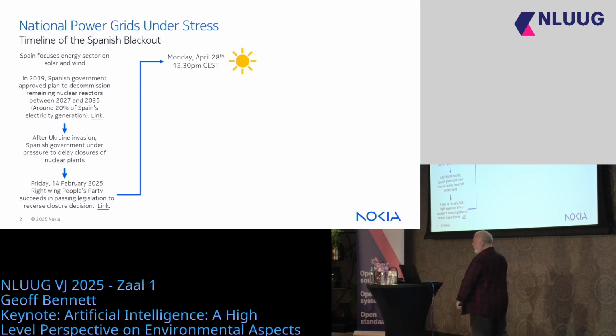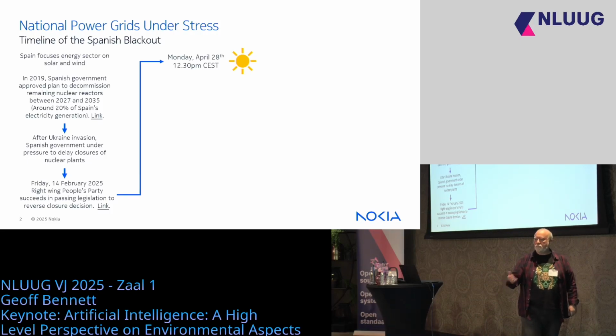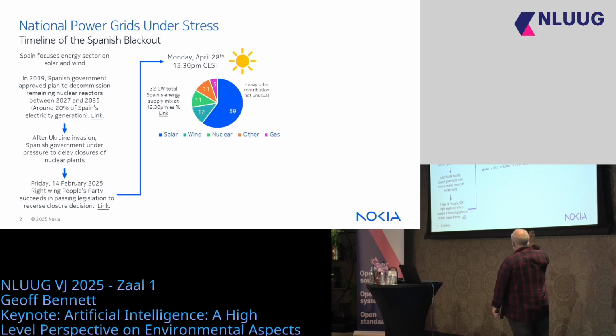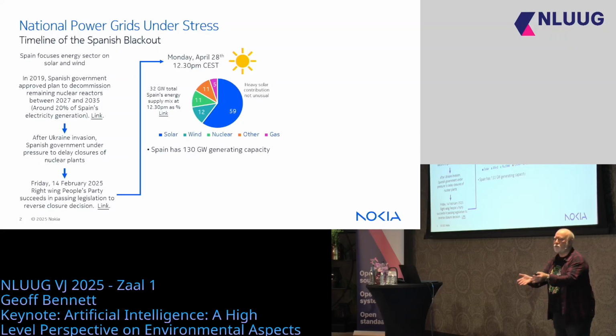So let's fast forward to April the 28th at 12:30 Central European Summer Time. What's happening in Spain? It's a beautiful sunny day. The energy mix in Spain is about 71% solar and wind. The rest of it comes from a little bit of natural gas, a little bit of nuclear. And if we look at Spain, they don't have a problem with the amount of power they can generate, right? That 32 gigawatts, that daily demand on that day, was fairly typical. And Spain can generate 130 gigawatts of electricity.